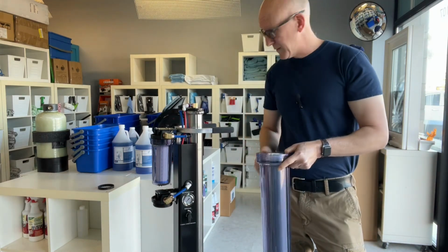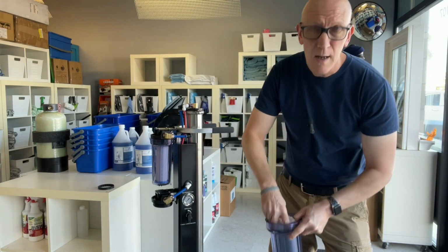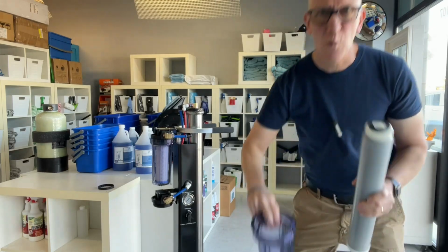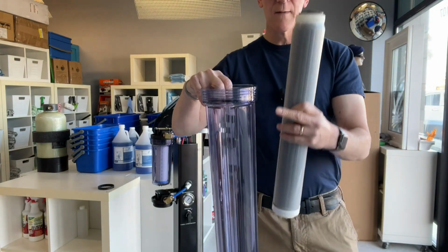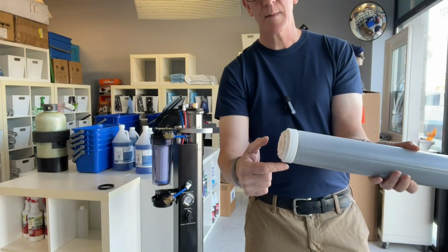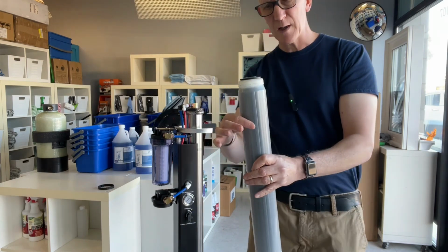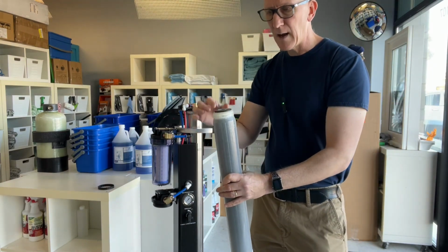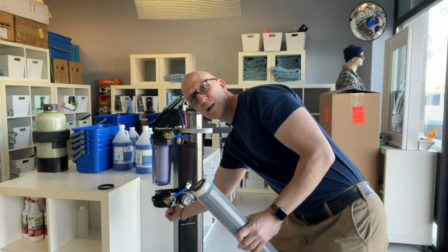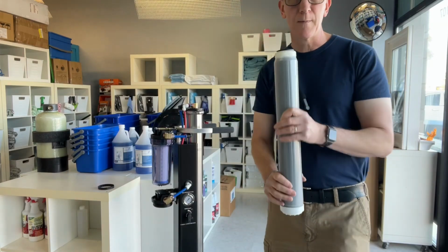It fits, right? So they put it all back and the thing doesn't function properly. In order for a DI cartridge to work properly, water enters into the housing and fills up. There are slits on the bottom of this end cap for water to go through, up through the DI, so it can do a final polishing of the water, and then finally through the center here to the output, where there's a center spindle inside here, and then it'll go to the output of the system.